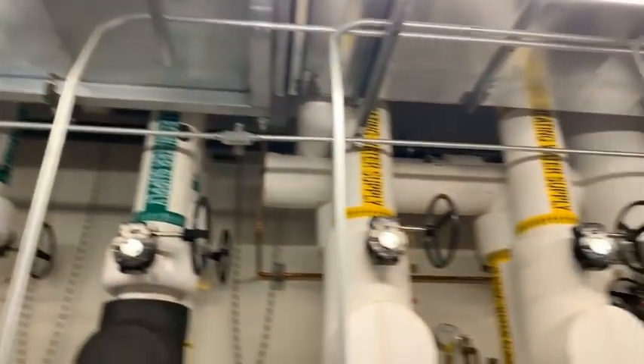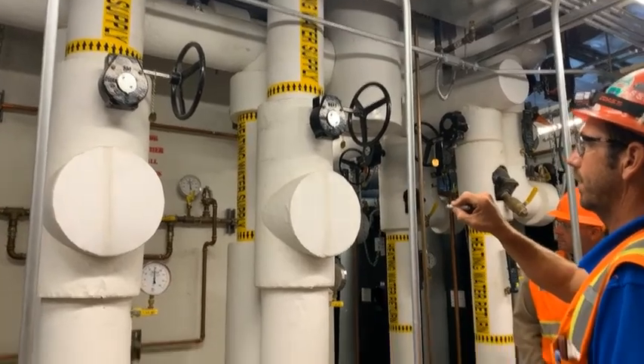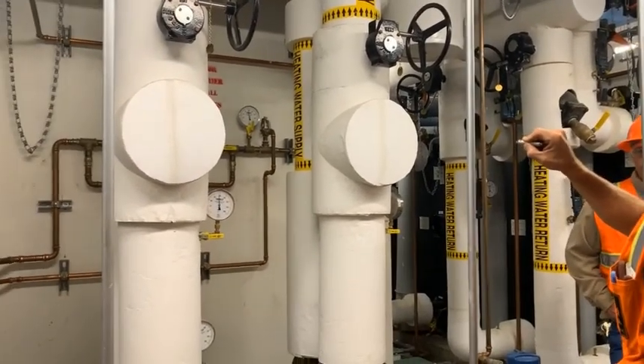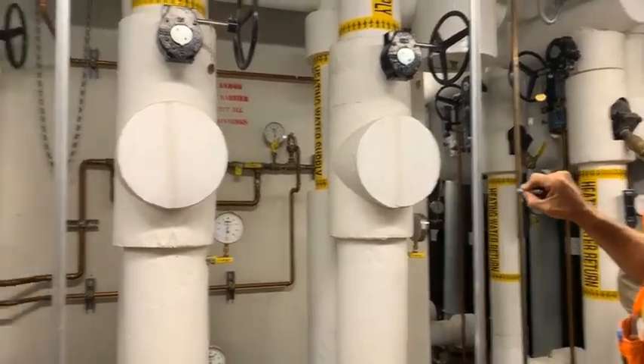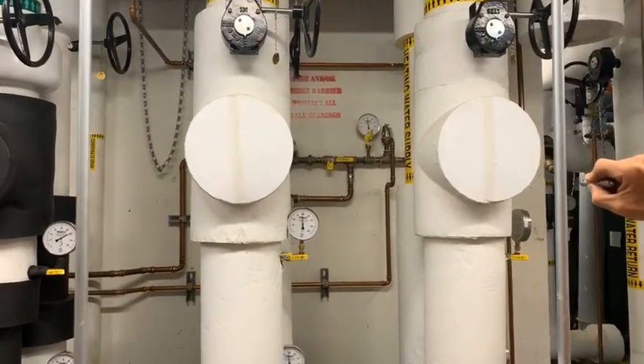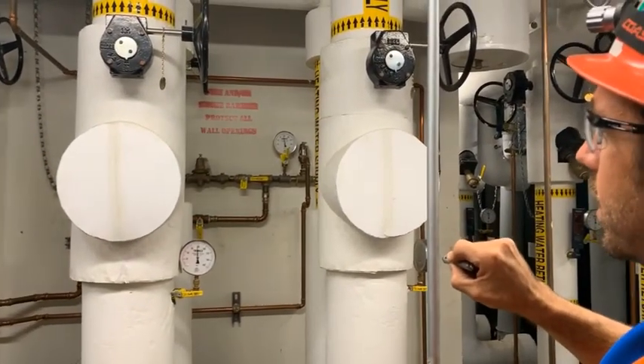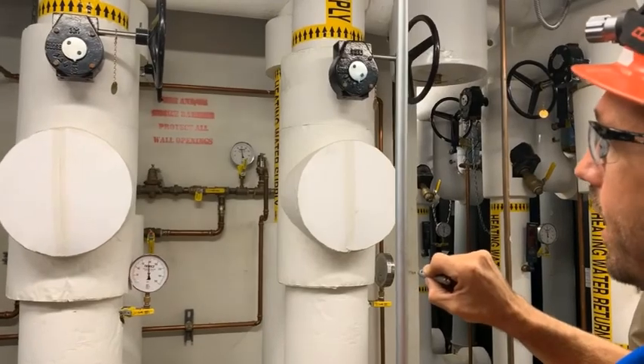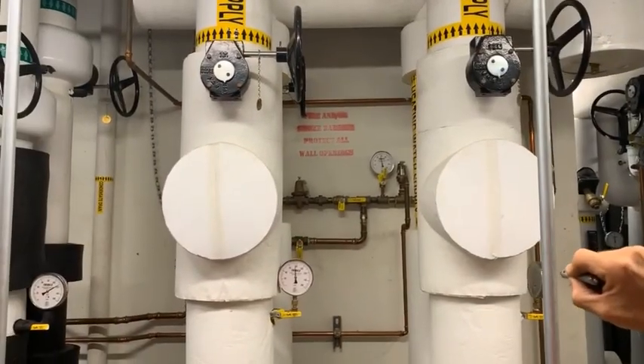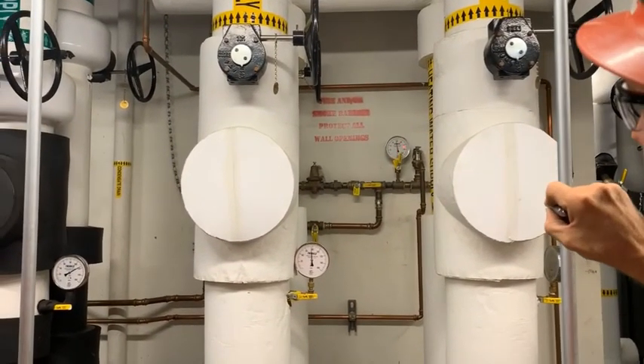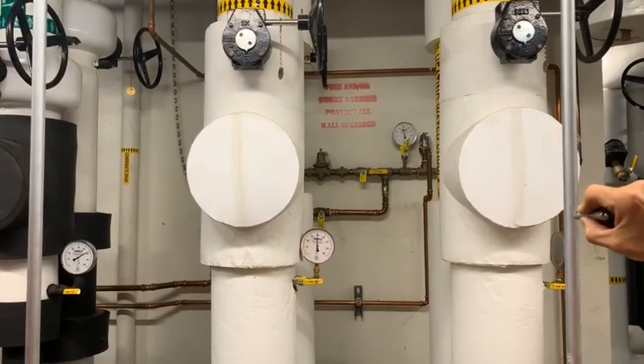Were you guys able to see the pressure reducing station over here for the heating hot water lift? I didn't get to talk about the line underneath it. The line underneath it will be a bypass. This bypass valve needs to be shut at all times. If you leave it open or if it starts leaking by, your outlet pressure will be your inlet pressure. We don't want that. Okay.